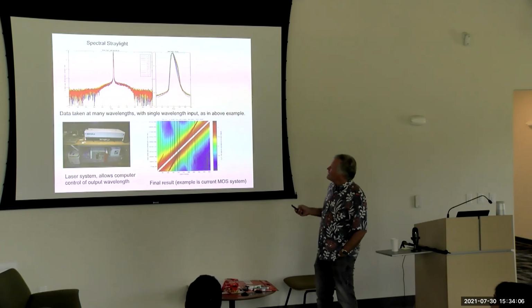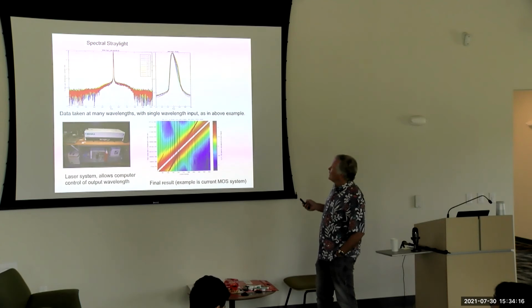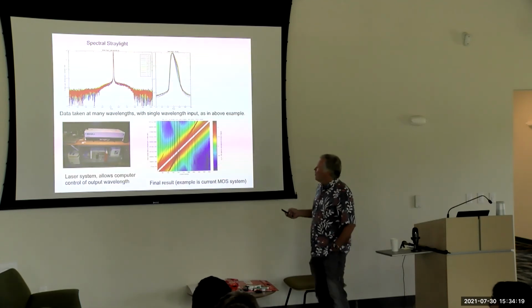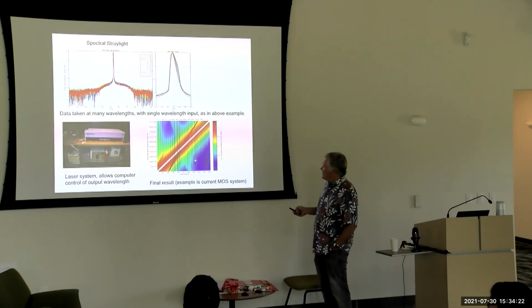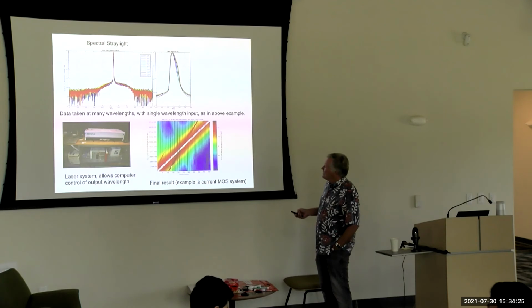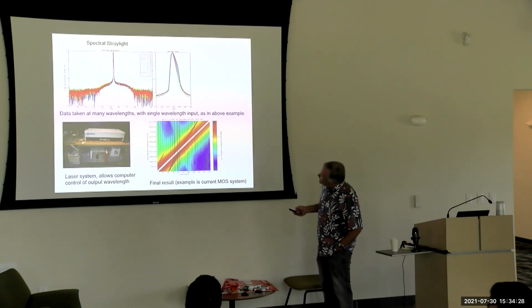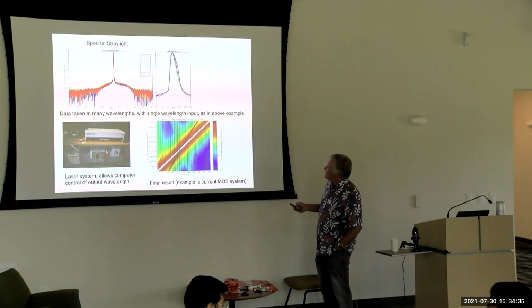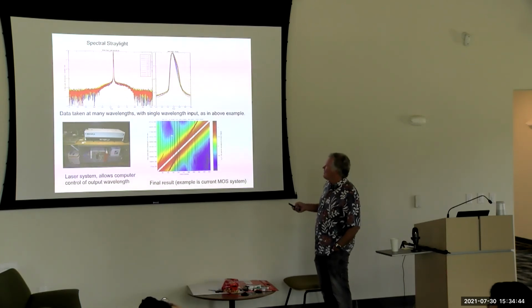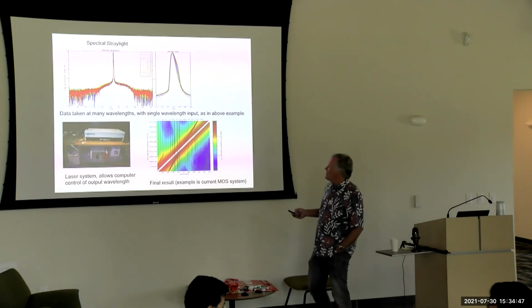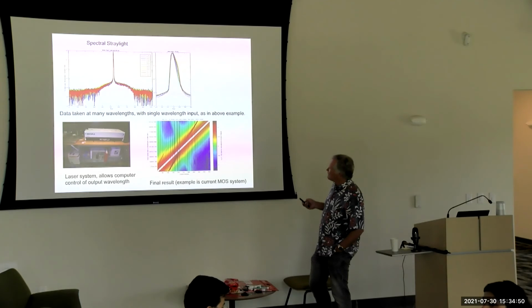Here's an example of some data normalized up here. You can see we're down about 10 to the minus 4, 10 to the minus 5 in stray light from there. Here's just the peak blown up. They do this at only certain wavelengths, and what you want to generate is a stray light correction matrix, which basically tells you, if I get light, so this is wavelength and blue spec, this is column number. If I send in light at this wavelength, then it'll be distributed across the array in a certain way. And so with this matrix, we can invert it and get rid of the stray light effect.